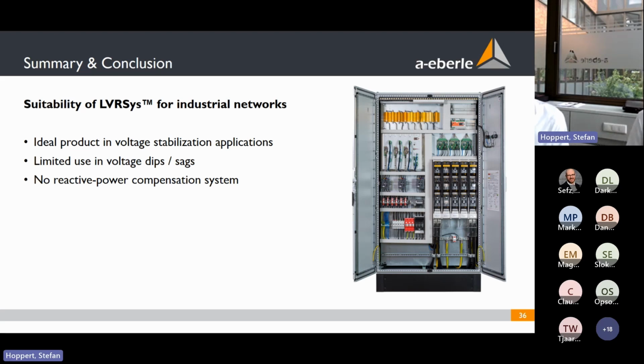Next question, is this device functional in the 3P 3W delta system? I don't know what it is. Do you know? Yes. For us, the three-phase system doesn't matter. We also have systems in the low voltage level in TT grids, so just three-phase, not a fixed star point from the transformer. We also have systems in the field where we have our own star point creator, because we are always controlled to the neutral point. If we do not have a neutral point because the grid is just a three-phase grid without the PE or N connection, then we create our star point ourselves.